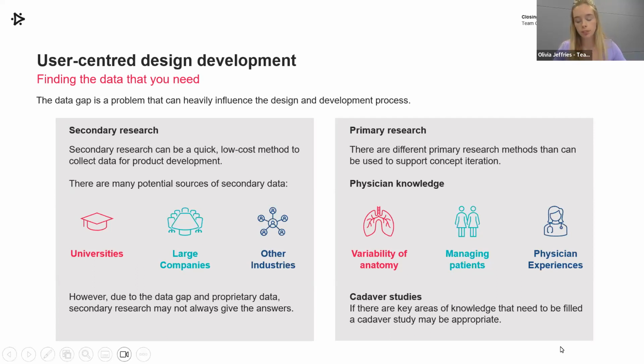If you still find that you have areas where you're struggling for data and you just don't have the key areas of knowledge that you need, a cadaver study may be appropriate. This is most commonly used in invasive devices where the anatomical context is very important to understand and very important to characterize. So in these situations where a user study just might not give you the data that you're really looking for, a cadaver study may be suitable.